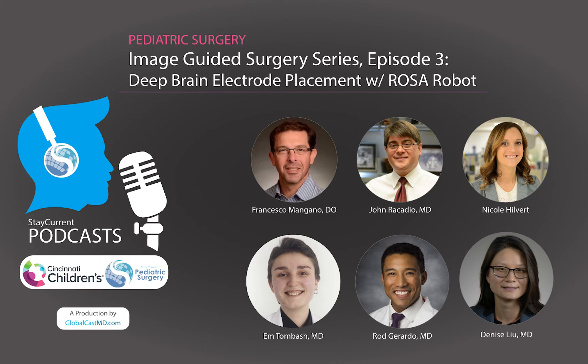For some patients we use alternative registration methods instead of facial registration — often when we have to place the patient prone, since you can't see the face at that point. The other approach is to insert screw bone fiducials into the skull, usually four or five of them. Then you spin a CT to visualize the patient's head and the bone fiducials, drive the robotic arm to each fiducial, and register them to the scan already loaded in the machine to achieve accurate registration.